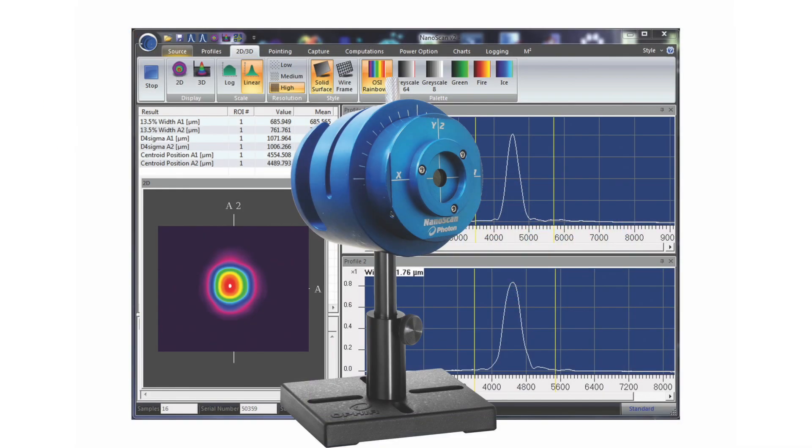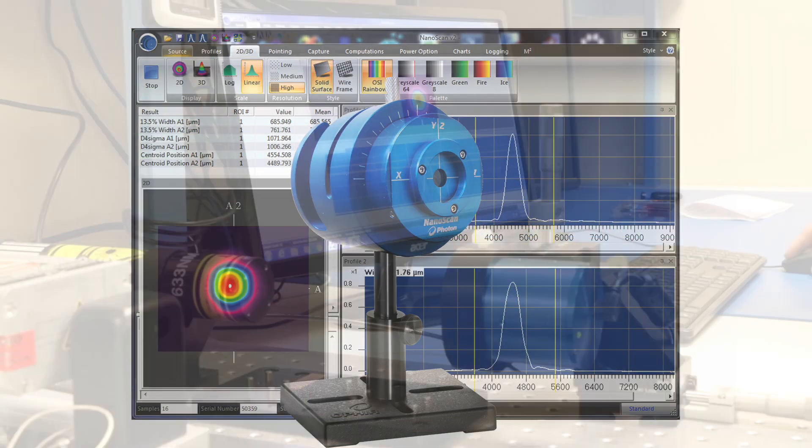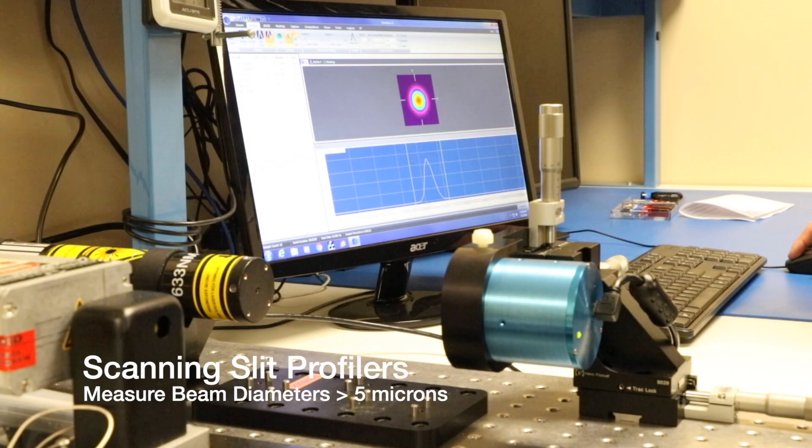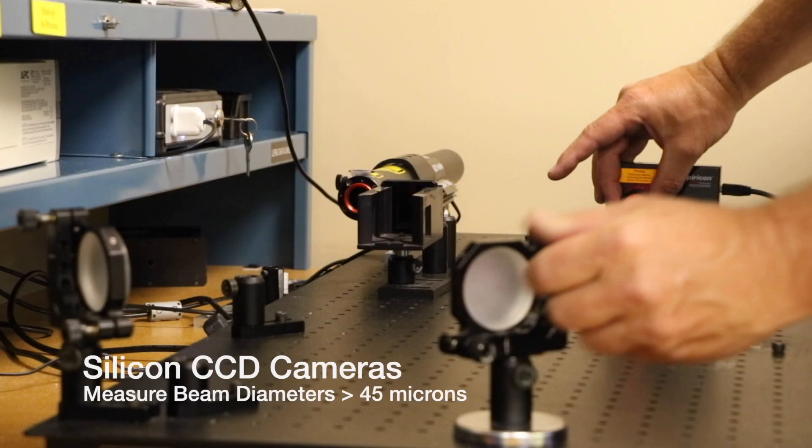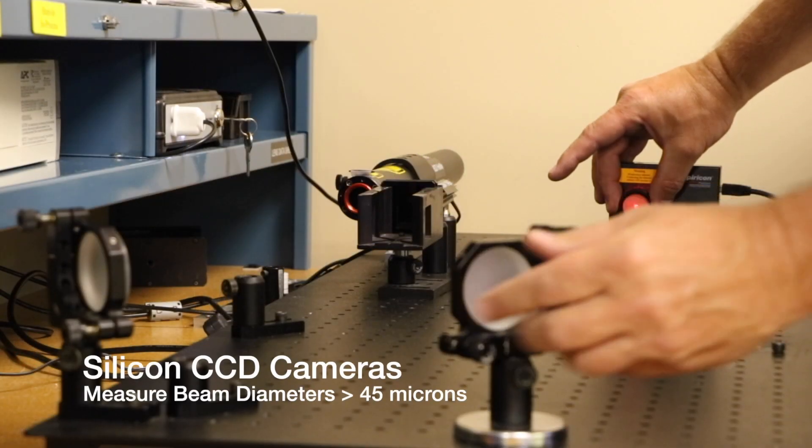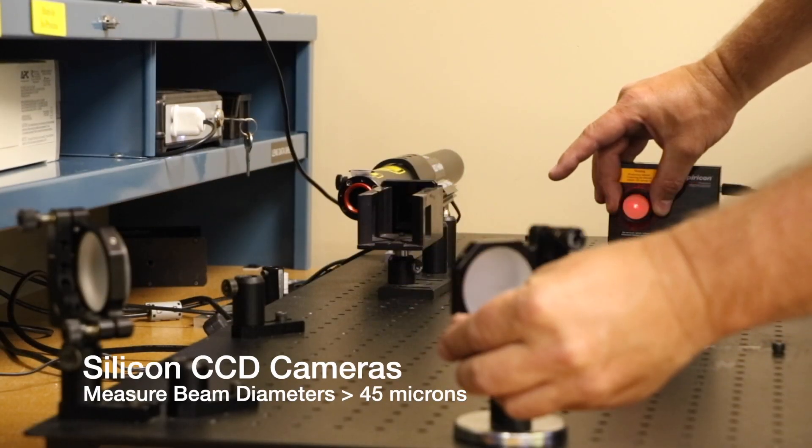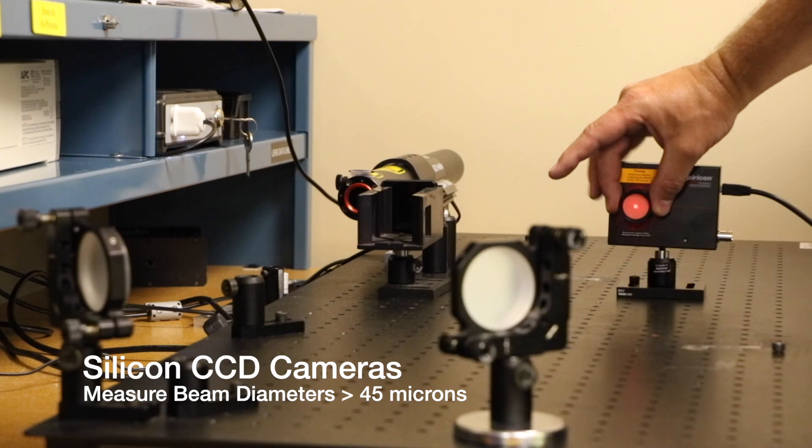Scanning slit profilers can make very accurate measurements of beam diameters as small as 5 microns, while cameras are limited to beams greater than 45 microns.